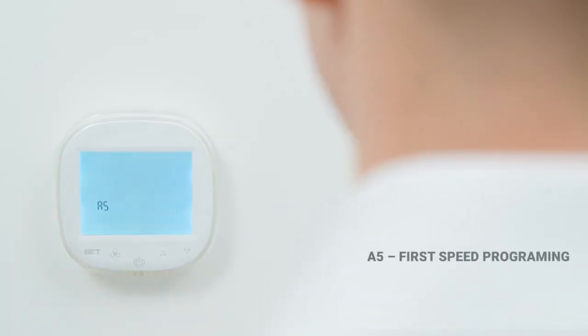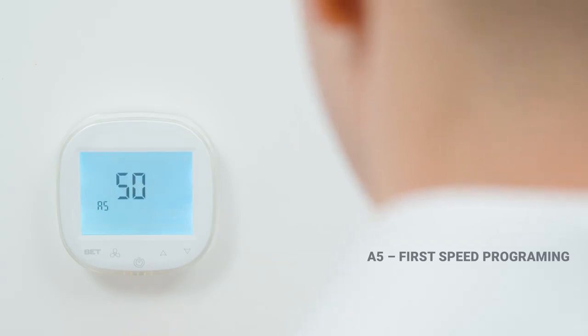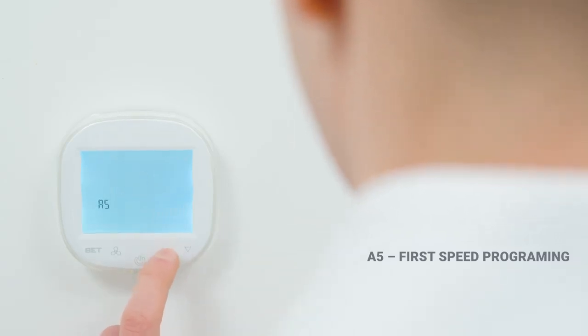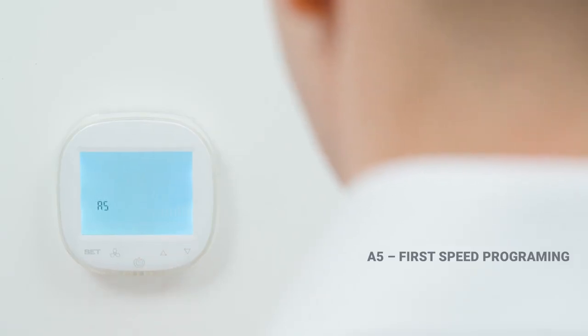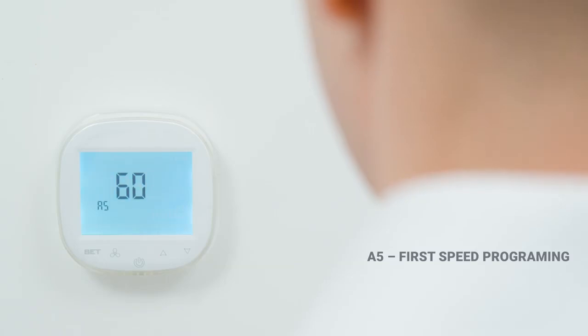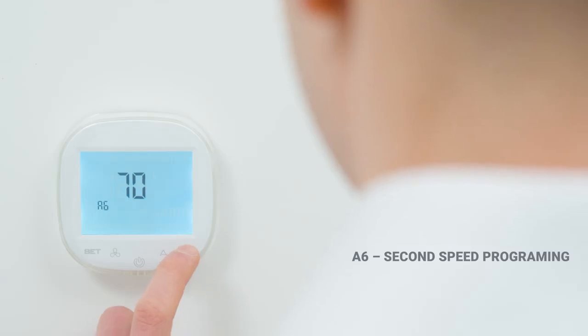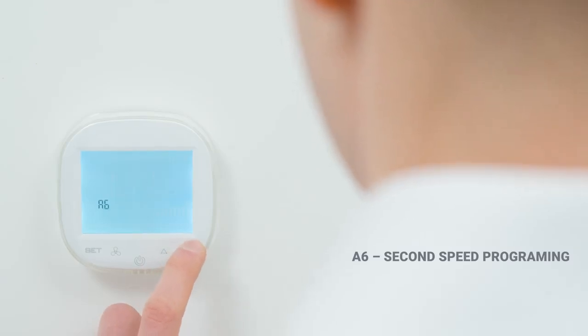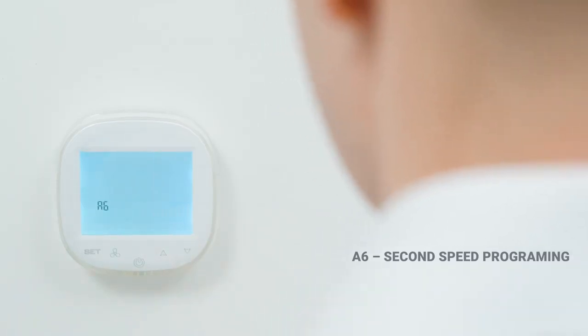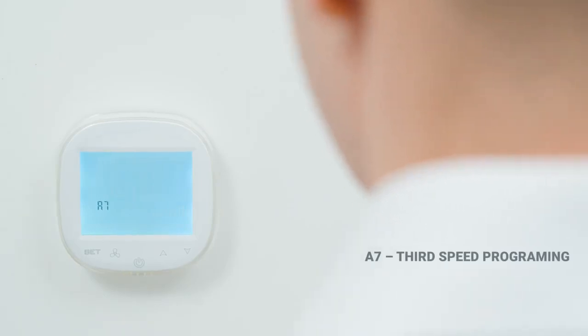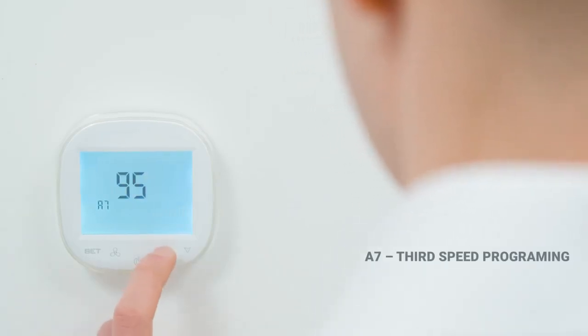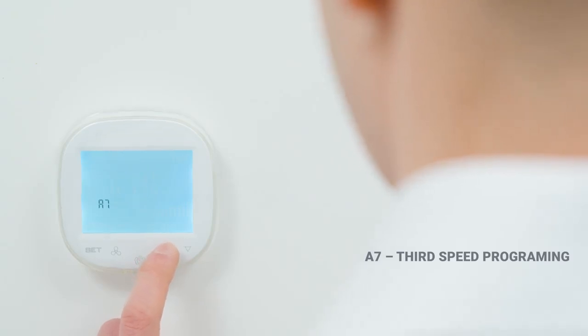Function A5: programming the speed value for the first gear. Select the value from the range from 15 to 80%. Function A6: programming the speed value for the second gear. Select the value from the range of 15 to 90%. Function A7: programming the speed value for the third gear. Select the value from the range of 15 to 100%.